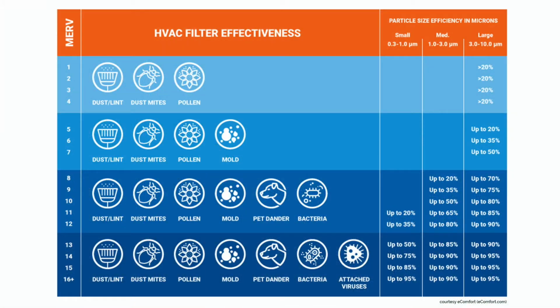While we agree that installing HEPA filters will provide for better containment of SARS-CoV-2, it's unlikely that your systems can support the additional pressure drop, or even physically fit deeper filters without supplemental filter housings and fan or motor upgrades. Fan-powered filter units could be implemented in a variety of configurations along with the associated balancing, power, and controls infrastructure upgrades, but that's likely also cost prohibitive.